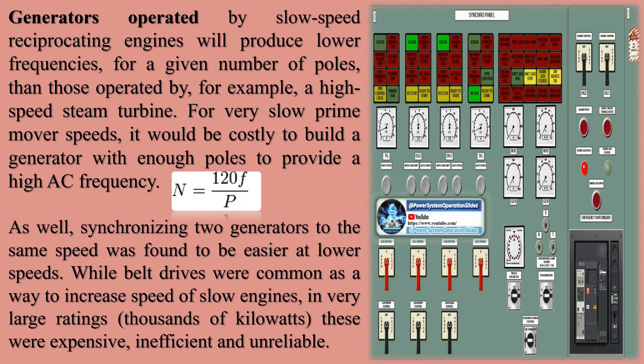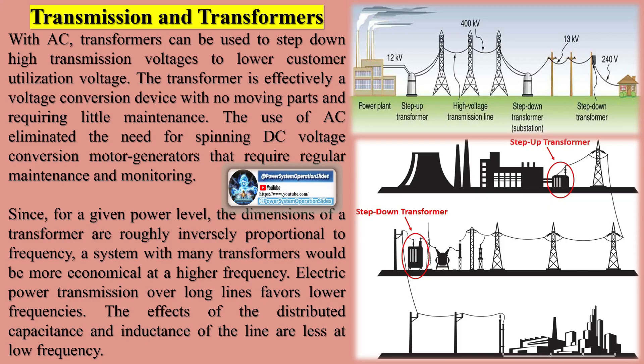While belt drives were common as a way to increase speed of slow engines, in very large ratings of thousands of kW these were expensive, inefficient, and unreliable. With AC, transformers can be used to step down high transmission voltages to lower customer utilization voltage. The transformer is effectively a voltage conversion device with no moving parts and requiring little maintenance. The use of AC eliminated the need for spinning DC voltage conversion motor generators that require regular maintenance and monitoring. Since, for a given power level, the dimensions of a transformer are roughly inversely proportional to frequency, a system with many transformers would be more economical at a higher frequency.